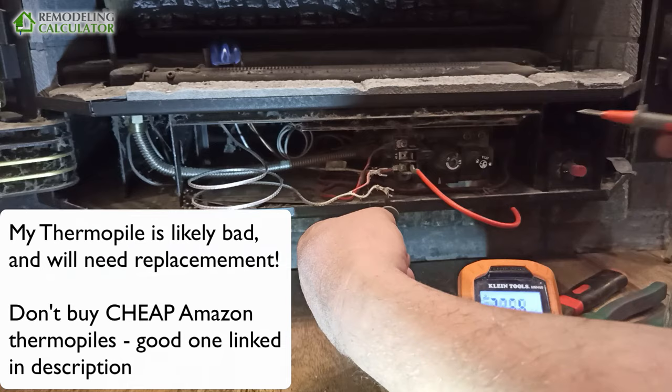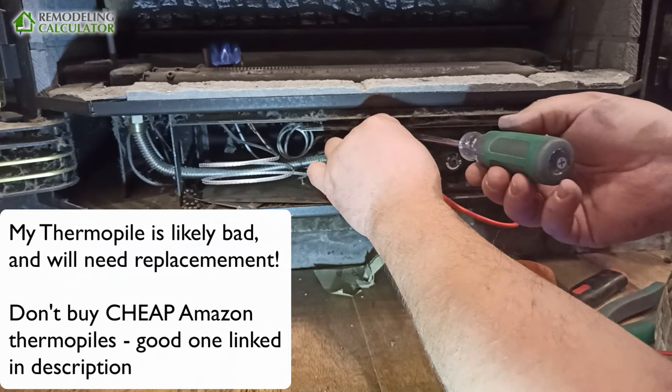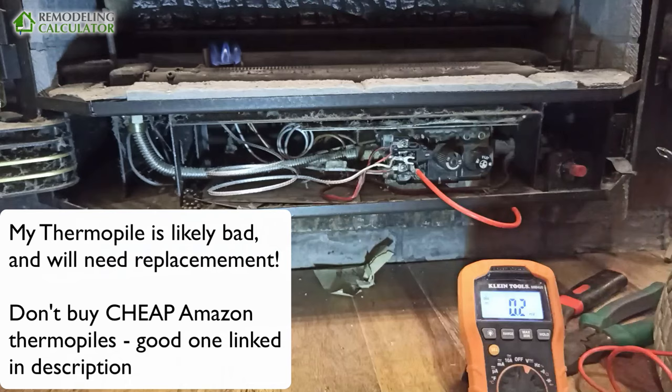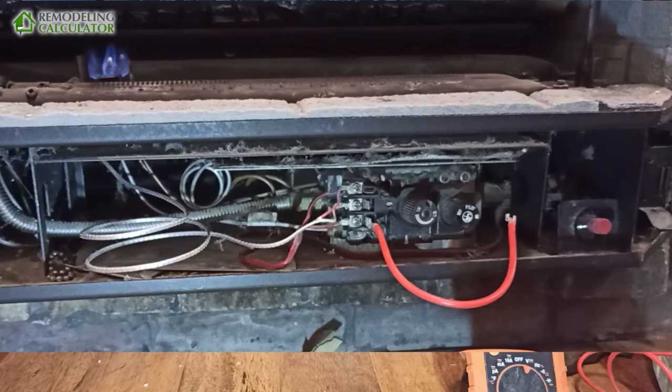That's a weak thermopile. Okay, maybe we need to replace it. Although it's new, this is cheap Chinese stuff from Amazon — you've got to get your thermopiles from a plumbing supply. It's doing the job ever so slightly.